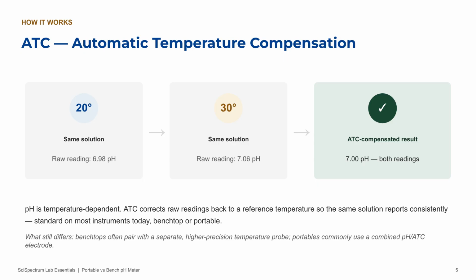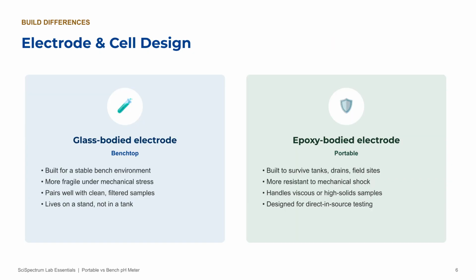Quick explainer on ATC, because people ask about this a lot. pH is temperature dependent, so the exact same solution can give you a different raw reading depending on the temperature. Here you can see it. 6.98 at 20 degrees, 7.06 at 30 degrees. Same solution. ATC, automatic temperature compensation, corrects that back to a reference temperature, so both readings land at 7.00. The good news is, this is standard on most instruments today, benchtop or portable. What still differs is the hardware behind it. Benchtops often pair with a separate, more precise temperature probe, while portables usually use a combined pH and ATC electrode in one.